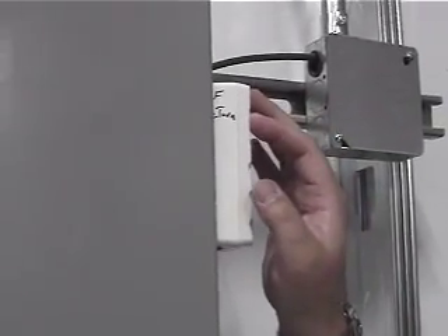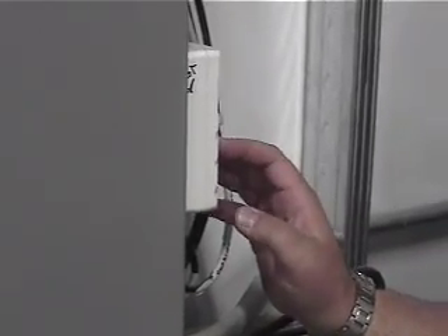So you've got your lab exhaust duct static right here. The probe is located on the back side as the duct comes up to the floor. When we go on the other side, I'll show you. Your duct static for your air handler is here, and your building static transmitter is here.